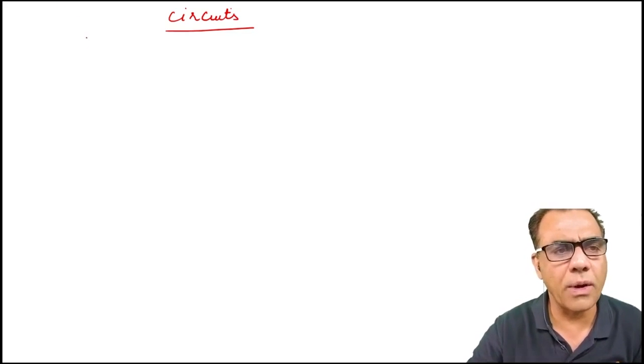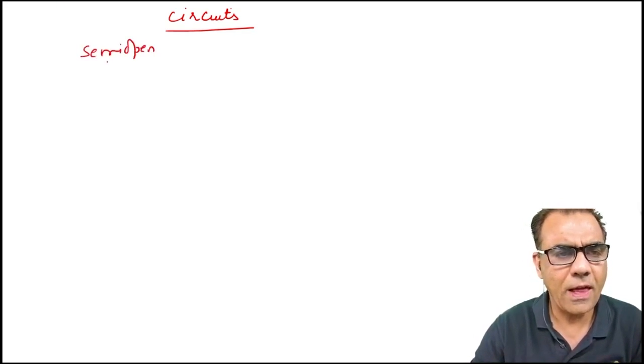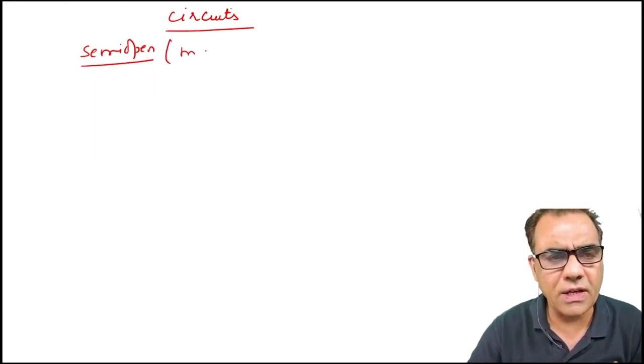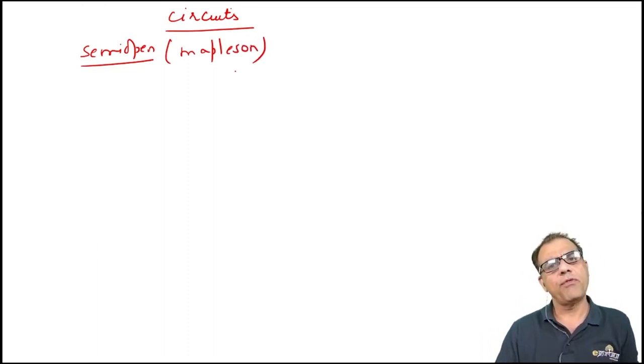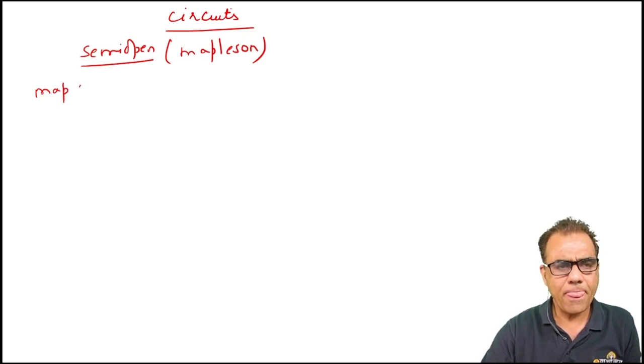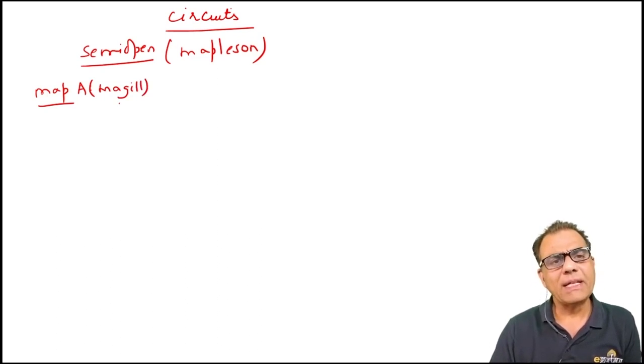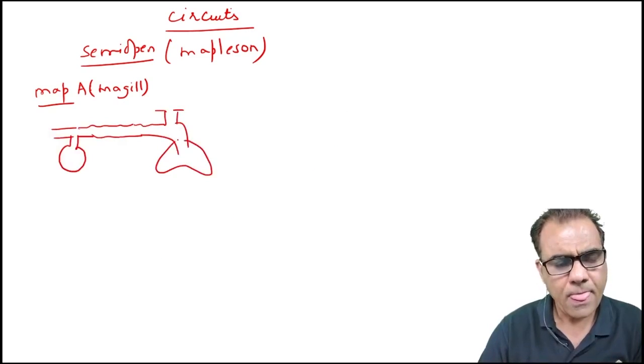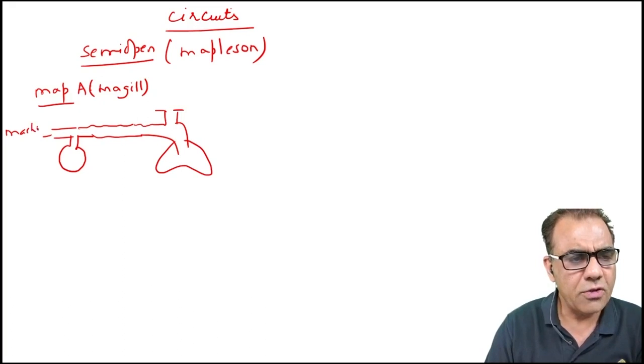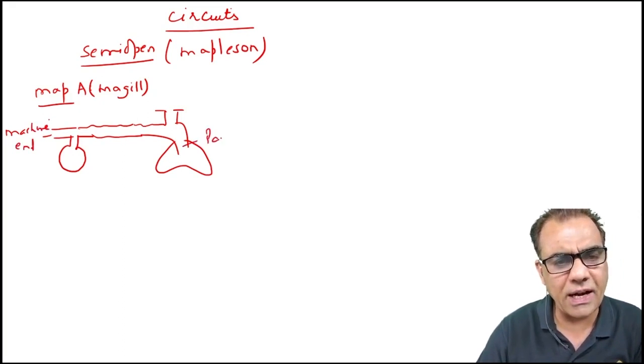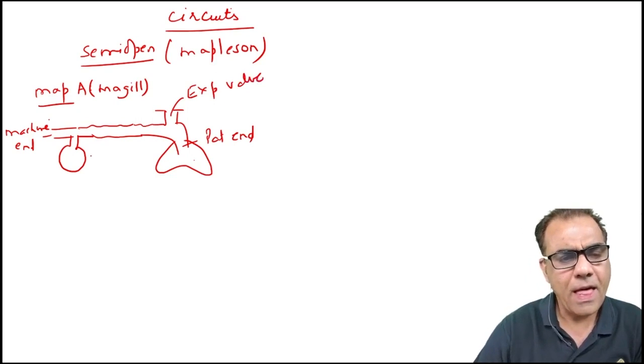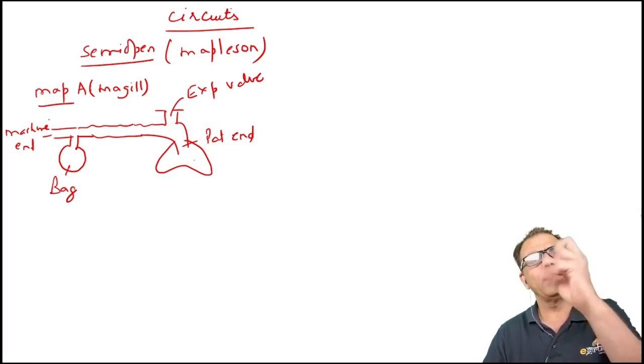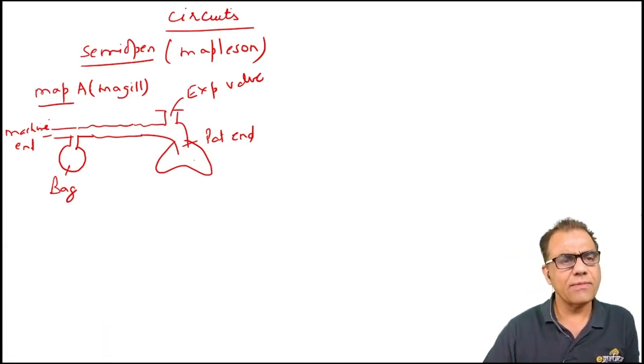So here let's first discuss semi-open. Semi-open circuits were described by Mapleson, so they are called Mapleson circuits. Mapleson A is also called the Magill circuit. So it is like this. This is the machine end which will be connected to the anesthesia machine, and this is obviously the patient end which will be connected to the patient either through a mask or through an endotracheal tube, and this is the expiratory valve, and this is the breathing bag which you will use to ventilate the patient. So the inspired gases coming from the anesthesia machine are called fresh gases.